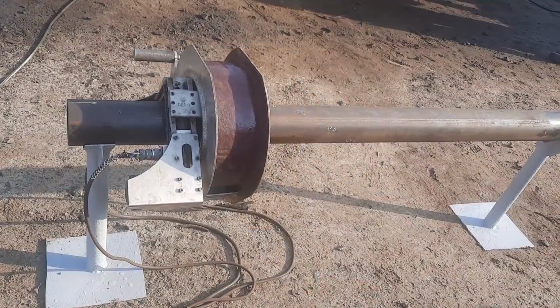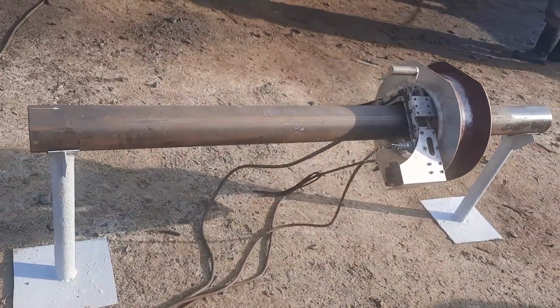There are 3 breakers, one is for the drive and one for the coil. If there is any short or something, the breaker will go off. So in that circumstance, you also have to check the breaker in the coil case and the drive case. If the buggy is not moving, first check the breaker, then the speed. If the speed is 0, the buggy will never move. So increase the speed. If there is still no movement, you have to check the breaker. If the breaker is okay and the buggy speed is high, but the buggy is still not moving, you have to check the cable system. That is the buggy troubleshooting technique.